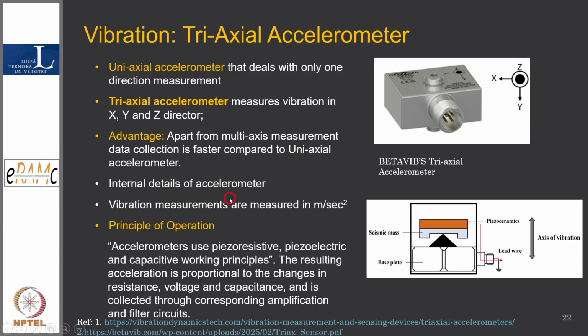The internal details of the accelerometer we are not able to see, but I will try to explain the basic concept - the principle of operation. We have a quartz or piezoelectric crystal, and when you apply a load from the material, it generates a current because electrons gather at one location, and that current is sensed. You saw a mechanical base plate, a mechanical load applied, and a seismic mass, let's say if we go into seismology, and that gives us a current which tells us the acceleration or velocity, whatever you are monitoring. This is the electrical side, and the motion of vibration is the x-axis here.